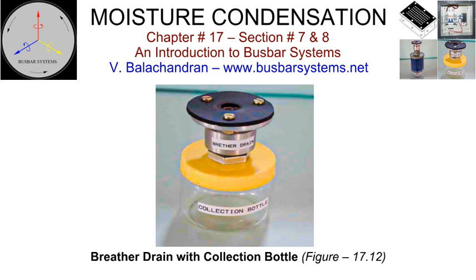Breather drains are available which, when fixed at the bottom, perform both the functions. Breather drains that can breathe 0.2 cubic feet of air per minute at atmospheric pressure and discharge 50 cubic centimeters of water per minute are available in the market. Breather drains are manufactured up to a degree of protection of IP68.